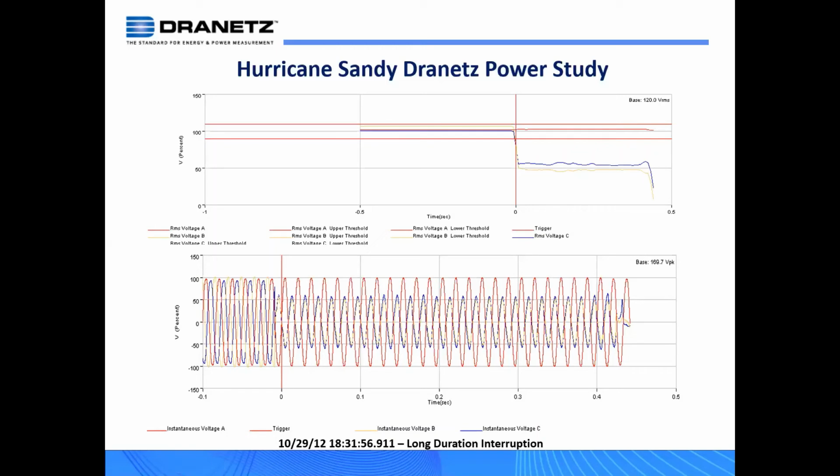All right, so this could be very damaging for equipment and motors that are still operating. We of course knew the hurricane was coming, so we shut down our plant that day, so we didn't run a risk of single phasing a motor. But this could be very damaging for a motor. This could be a safety issue as well.